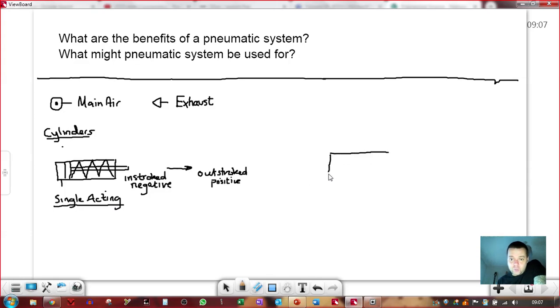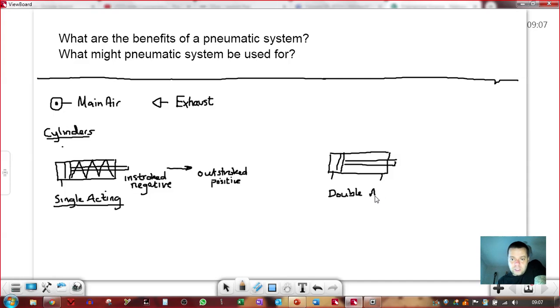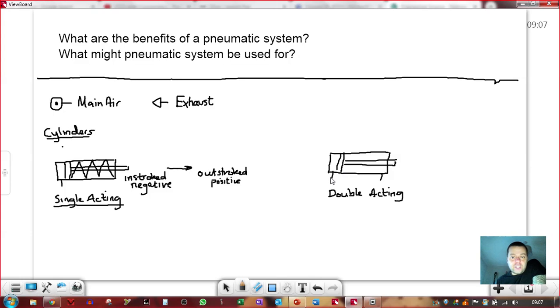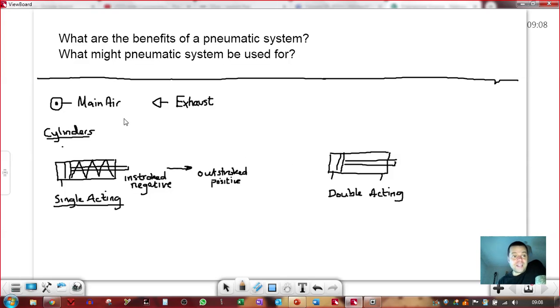The other one is a cylinder that has no spring inside it. The same terminology applies in terms of in-stroke and out-stroke, and the symbol starts off the same. This one has two ports and it's called a double acting cylinder. This means that you need air to out-stroke it and you need air to in-stroke it, so it requires a little bit more complex control. You can imagine that if you provide an air signal on one side it'll out-stroke. If you turn that air signal off and remove that pressure, the cylinder will remain out-stroked — unless something acts on it like gravity or the weight of something. If you want to in-stroke it, you have to provide an air signal on the other side, and you'll only be able to in-stroke it if the signal on the out-stroke side is gone.